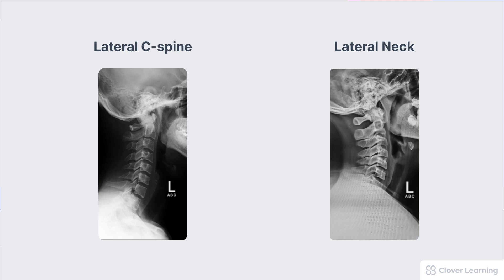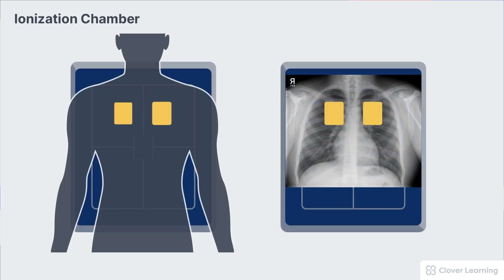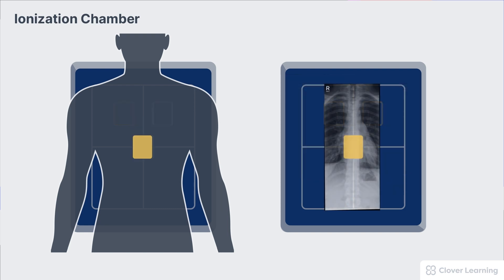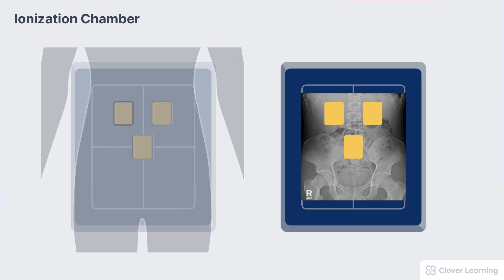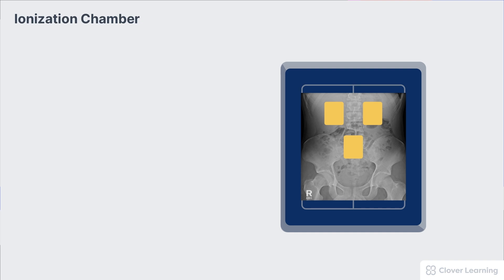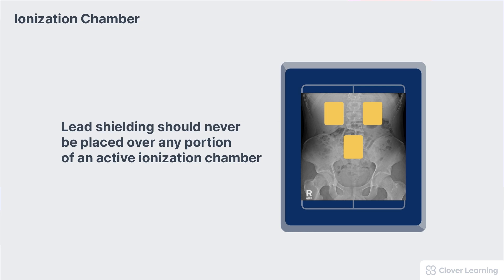This is also why it's very important to activate the correct AEC cells, as it differs for different body parts. For a chest X-ray, you would activate the outer two cells over the lung fields, since the lungs are the primary organs of interest. For a thoracic spine, you would activate only the center cell under the thoracic spine — we want a good exposure of the spine, not the lungs. For the abdomen, you would use all three cells to ensure the entire abdomen is correctly exposed. Additionally, lead shielding should never be placed over any portion of an active ionization chamber, as this would slow the flow of x-rays into the cell and significantly increase exposure time and patient dose.